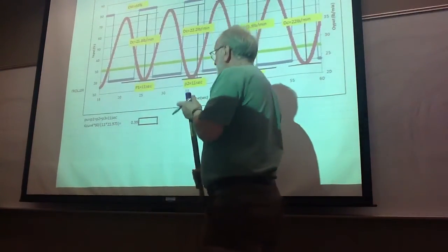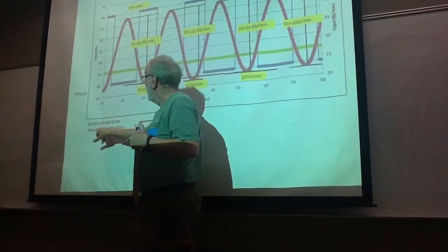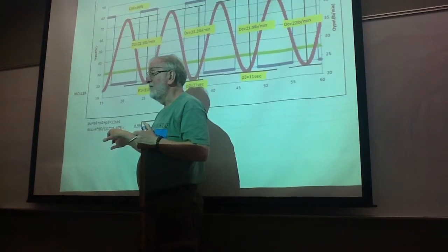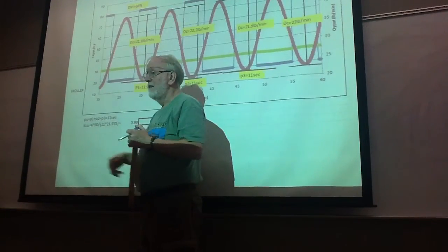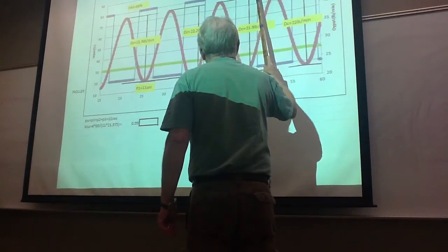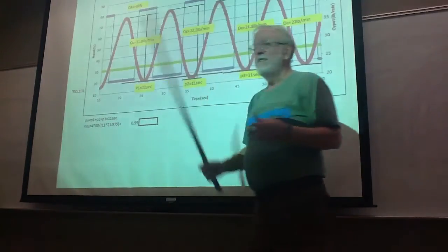Delta C for this system has what units? Can you tell, Joe? Pounds per minute. So if delta M is percent and delta C is pounds per minute, what are the units of this going to be? Percent per pounds per minute. So the units are upside down. I suspect the KCU is upside down, but I wouldn't guarantee that.